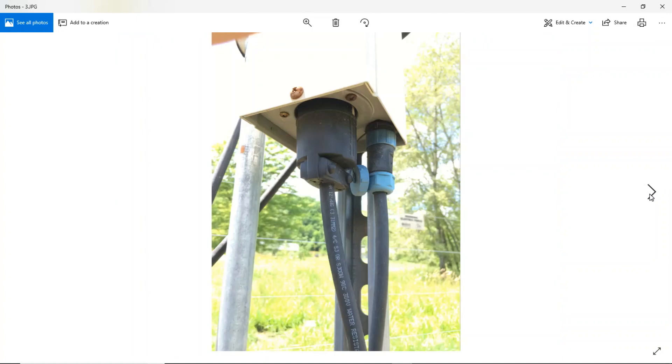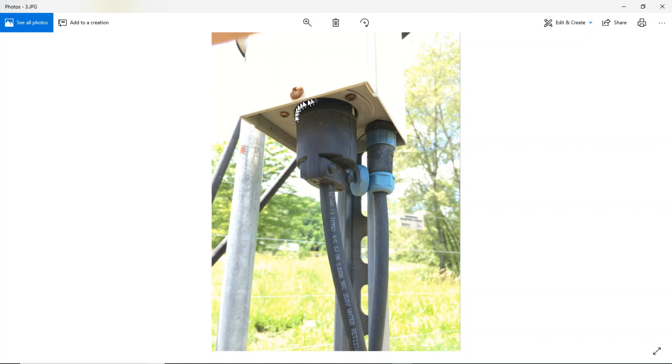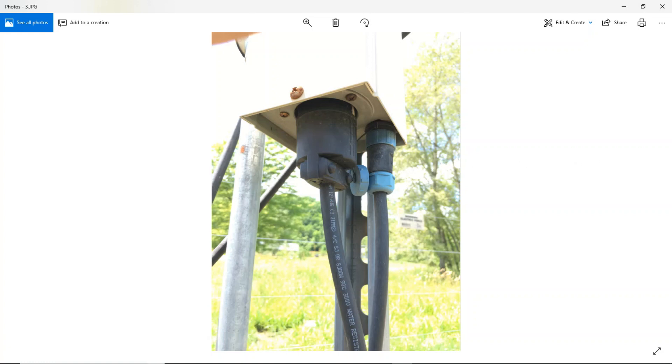Power from the generator and control circuit both plug in. This is an aircraft connector, an electrical aircraft connector. It goes down to the pressure switch that I just showed you, and that goes up to the relay box on the very top of this power pole. This is the 30 amp 120/240 twist lock. It's a four pole connector. This whole assembly is the ground because it's everything else. So I don't really have a dedicated ground rod.